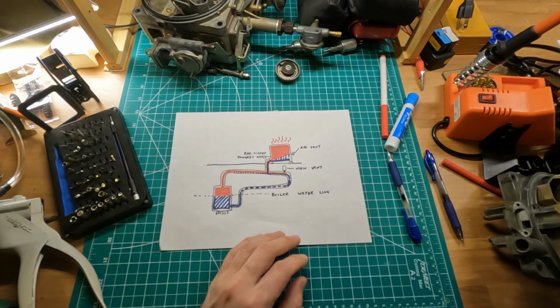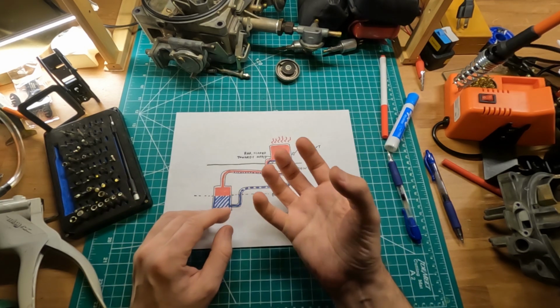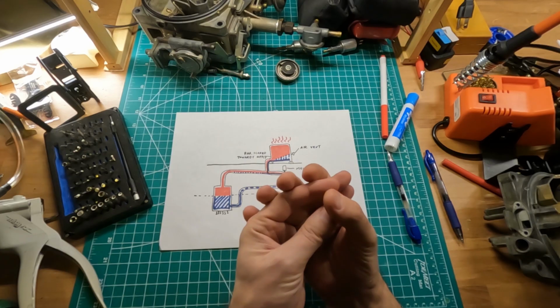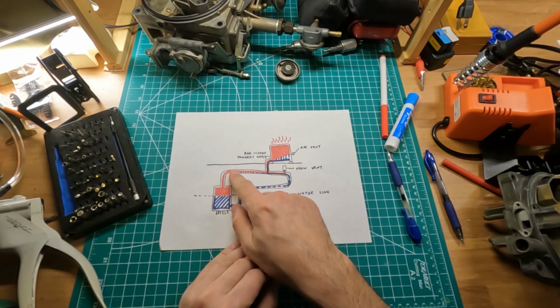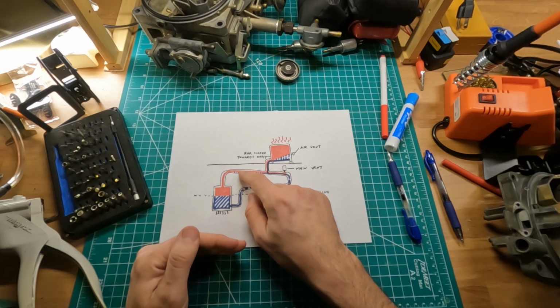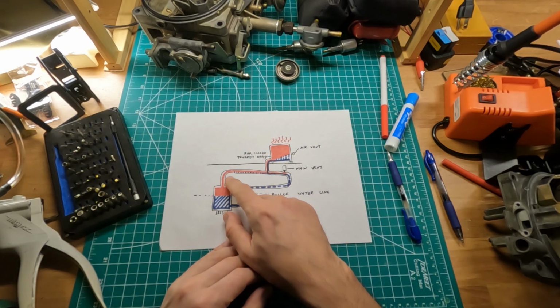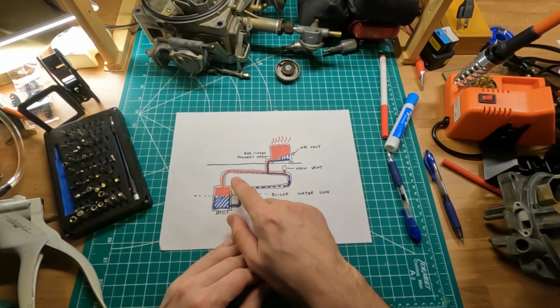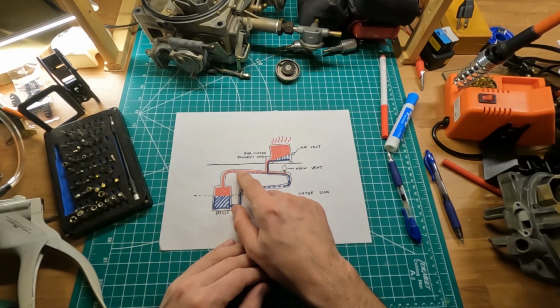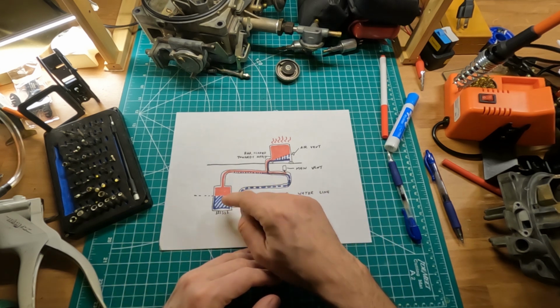Now, as the hot steam touches cold pipes, by definition, the steam condenses a little bit. So there's a transfer happening. The steam warms up the pipes, at the same time loses some of its steamness, to use a totally colloquial term, and then you have this water condensate, and this condensate has to somehow return back into the boiler.